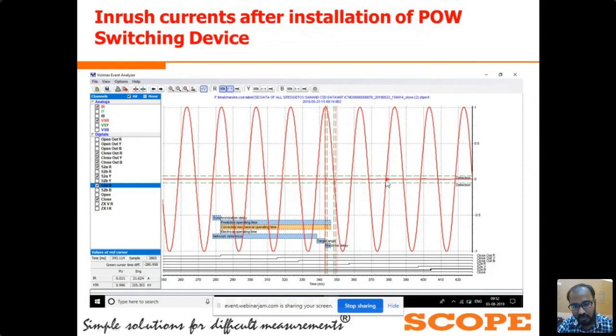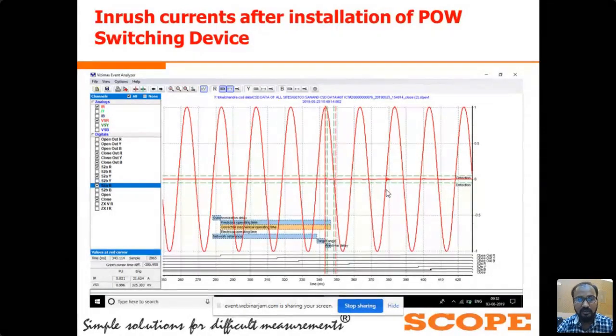After a few milliseconds, you can observe there is another spike. This spike is due to the Y and B phase getting closed after this much delay. So we have used the delayed closing strategy. After a few milliseconds, near to 1.5 cycle, you can observe another spike, which is due to the Y and B phase close. So for the power transformer application, we have reduced the inrush current from 3 times of full load current to 0.003 pu.